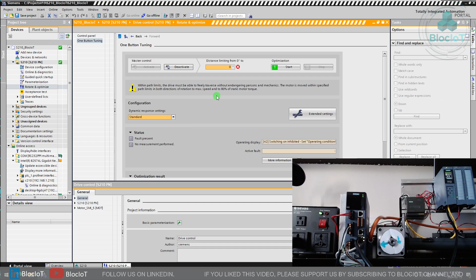You can configure your PID parameter within your drive automatically. You don't need to manually do that. So to do that, we go to one button tuning. Again, you need to activate the master controller, the drive. Same, give it a monitoring time. And you can select different ways to do that, but for now we just leave it for default. I'll just give it 360 degrees, maybe just to limit the rotation of the drive, and hit the start.